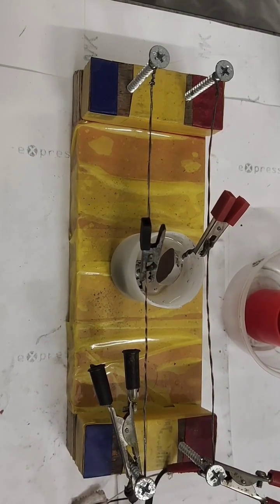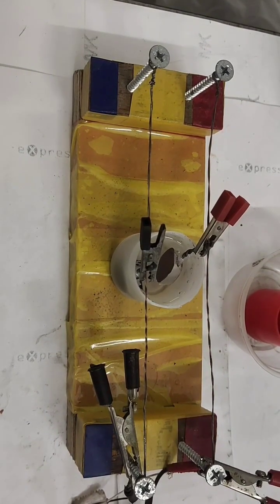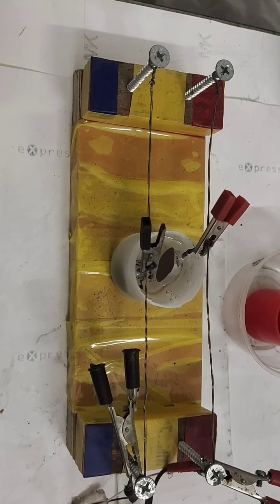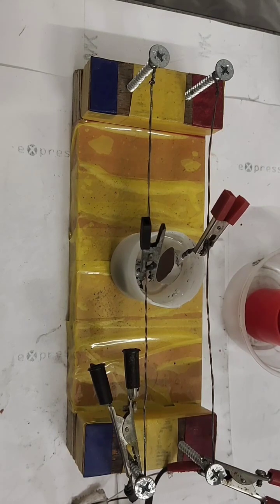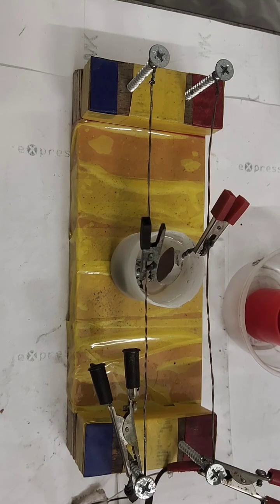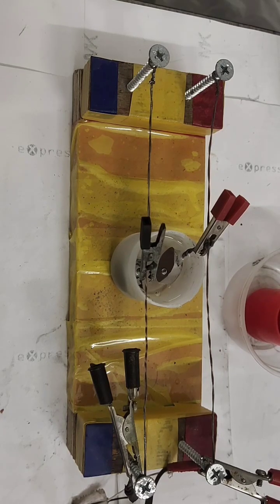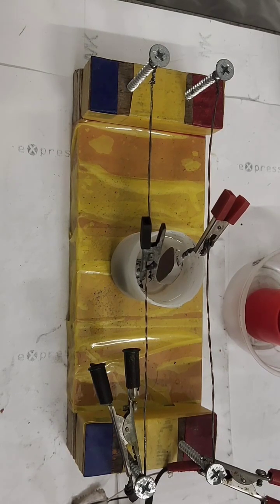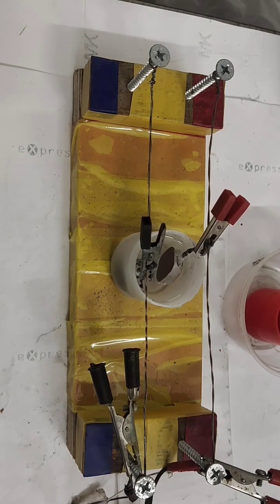This forming we have to go for one hour, then we will switch off the DC supply, then go for discharge of 10 minutes using any small motor. Again we will go for forming one hour, again discharge for 10 minutes.